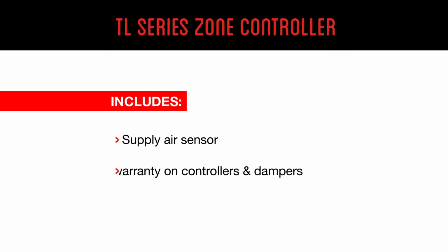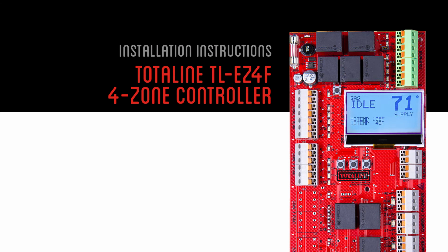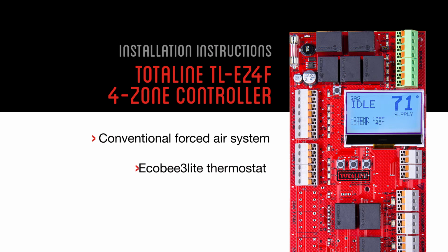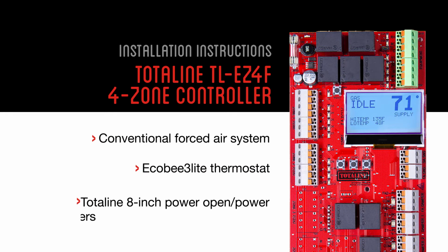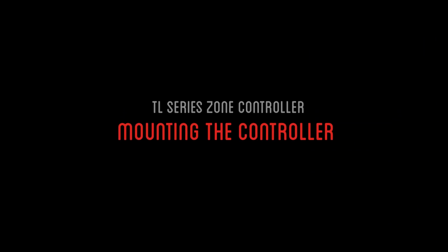Totaline controllers come with a supply air sensor and a 5-year warranty on both the controllers and the dampers. Be sure to check the compatibility of all devices prior to installation, and note that the supply air sensor is required for the system to operate. In this video, we're installing the Totaline TL-EZ4F 4-zone controller to a conventional forced air system with an Ecobee3 lite thermostat and Totaline 8-inch power open, power close 3-wire dampers.